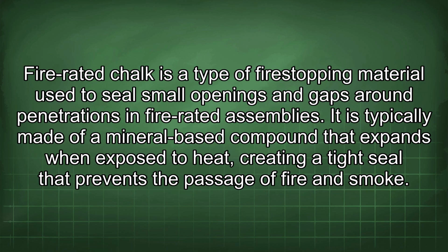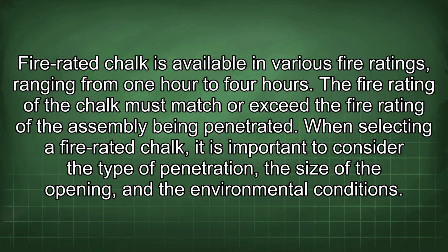Fire-rated caulk is a type of fire-stopping material used to seal small openings and gaps around penetrations in fire-rated assemblies. It is typically made of a mineral-based compound that expands when exposed to heat, creating a tight seal that prevents the passage of fire and smoke. Fire-rated caulk is available in various fire ratings ranging from 1 hour to 4 hours. The fire rating of the caulk must match or exceed the fire rating of the assembly being penetrated.